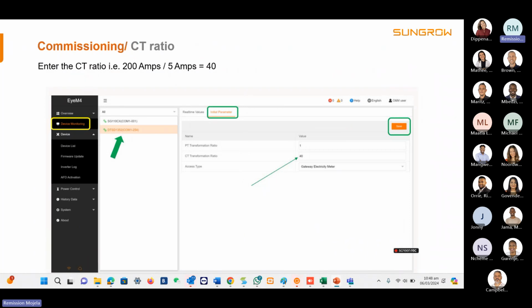And then after that, you go to the meter, you go to device, or you call initial parameters on the meter itself. That's where you actually set the CT ratio. So you don't need to change anything on the meter. You can directly go to the iSolar Cloud and change the CT ratio so that the system can see how much you're actually drawing from the grid or pushing back into the grid.